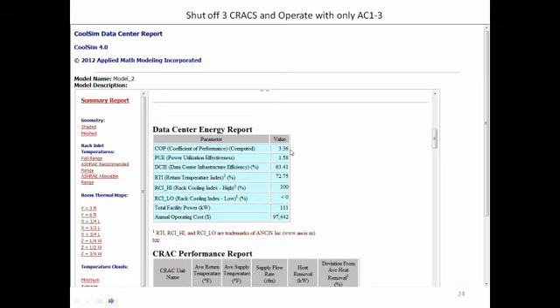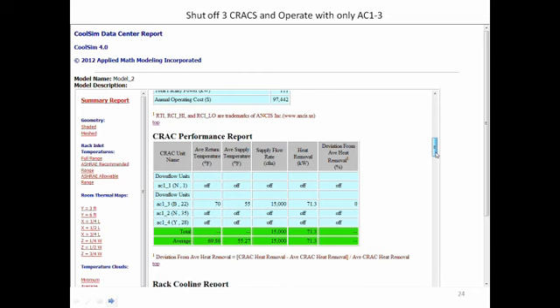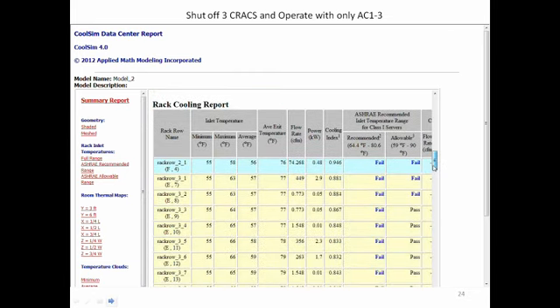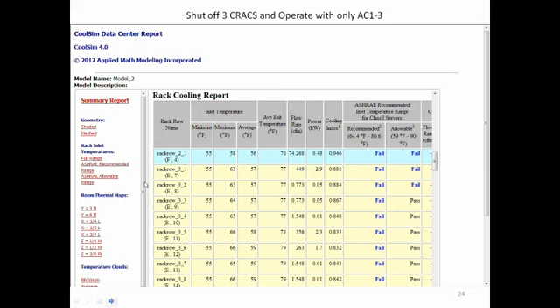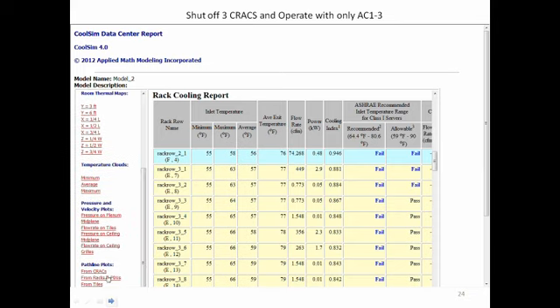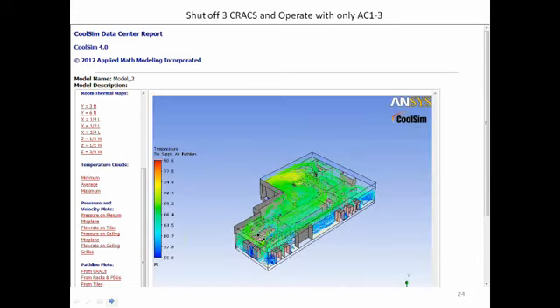Now, these were current measurements made by the customer. So all I did in these calculations is, in the first run, I used all of the CRACs, used the current supplying them all. And in this one, I used just the wattage supplying one of them. And guess what? COP moved way up because I turned the fans off and turned the pumps off on the other units. So things got a lot better. Still too cold, but the operating cost dropped to under $100,000 from 140. Still running it at 55, still too cold, but if we take a look, Liz, now at the same chart, the same plot of flow rates from the tiles, you'll see that it's a lot less of a hurricane.